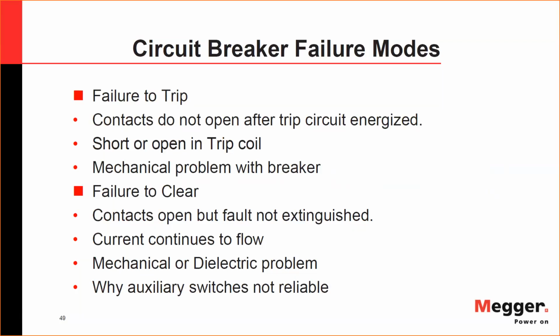Maybe because of a mechanical problem, it did not open fully. It was only open for a short gap, or because of a dielectric problem. It opened, but the dielectric inside was not very good, or was not maintained correctly, and the current still continued to flow through the dielectric.